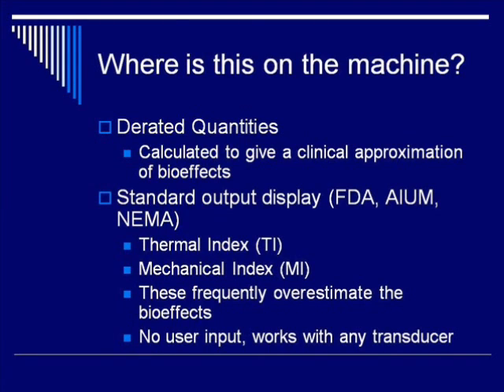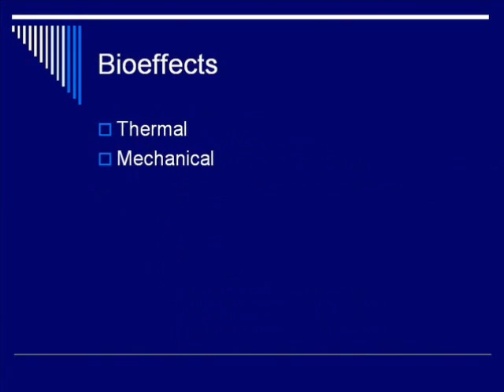The two quantities we'll be discussing are the thermal index and the mechanical index. These numbers frequently overestimate the possible bio-effects. They're built to be very conservative, and so it's important to consider that when you're using these in your clinical practice. They require no user input and work with any transducer. They're usually displayed in the upper right or lower left-hand corner of the display on your ultrasound machine. We'll come back to those indices after we discuss the bio-effects themselves.